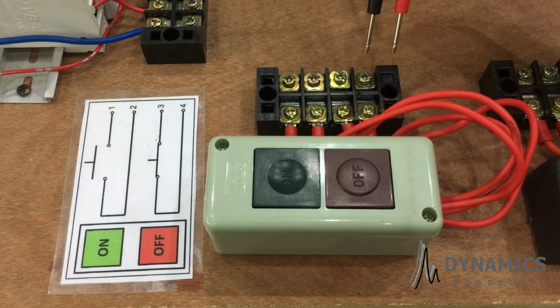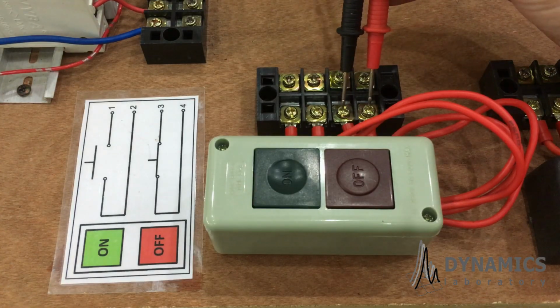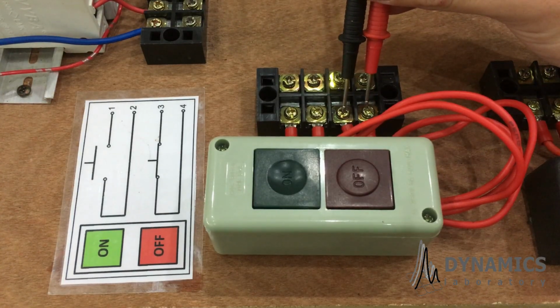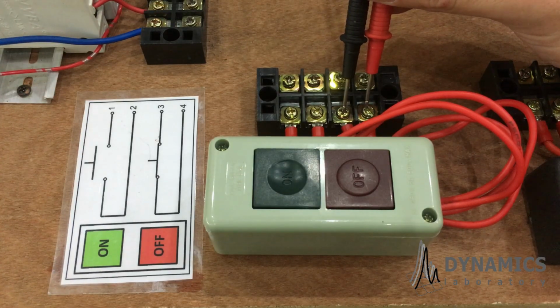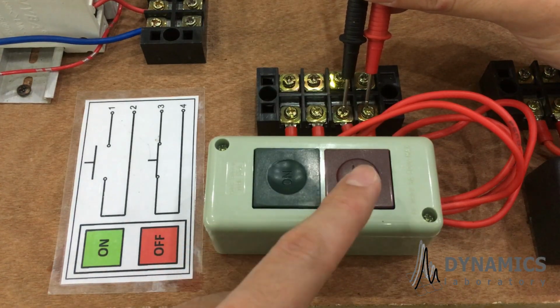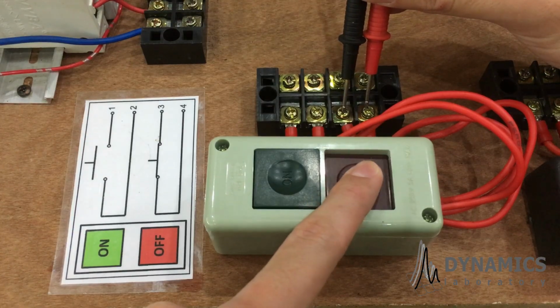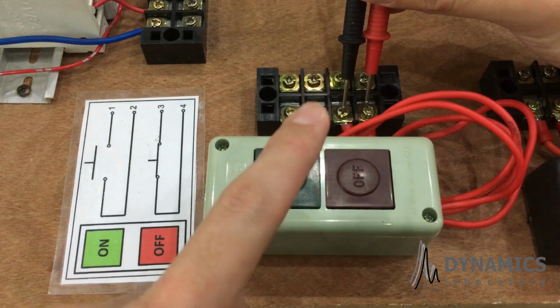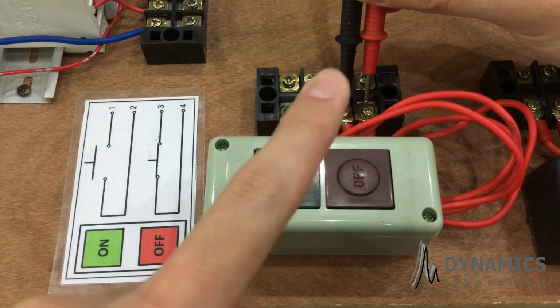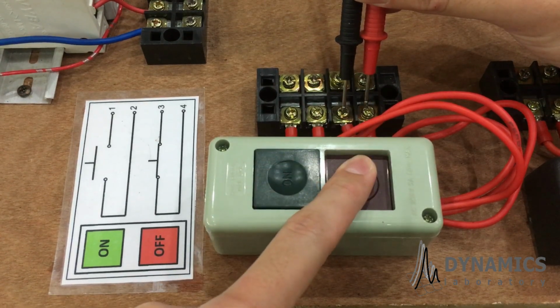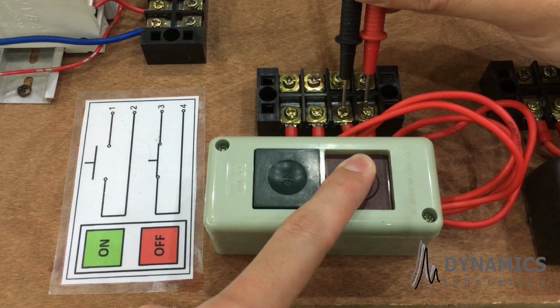Let's try leg number 3 and number 4. Leg number 3 and number 4 are normally closed. That's why if we test it with the buzzer, the buzzer will sound. But if I press this button, the buzzer will not sound, because the normally closed circuit is changed to normally open.